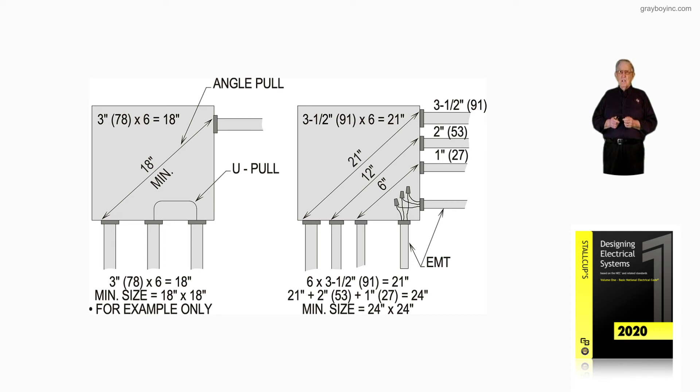Notice the EMT coming in below. That's just illustrating that if you're pulling number 12 wire, then you don't have the same kind of radius bend. If you were pulling number 10 in that EMT, you can still make joints there or even make a bend with it real easy. Just with your finger you could make the bend. Where the others, you've got to take both hands in some cases, depending on the size of the conductor.